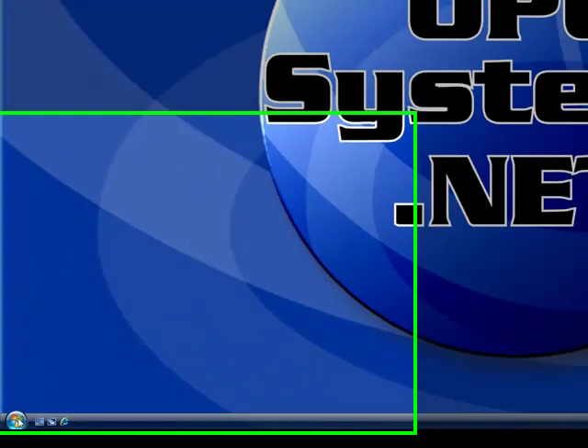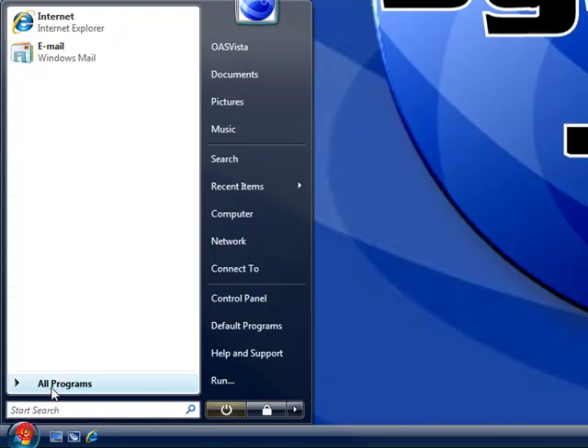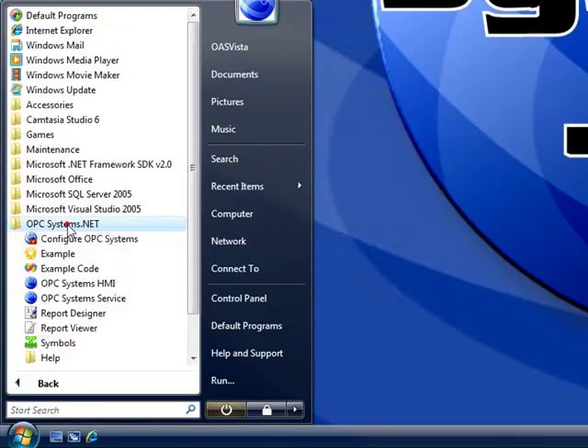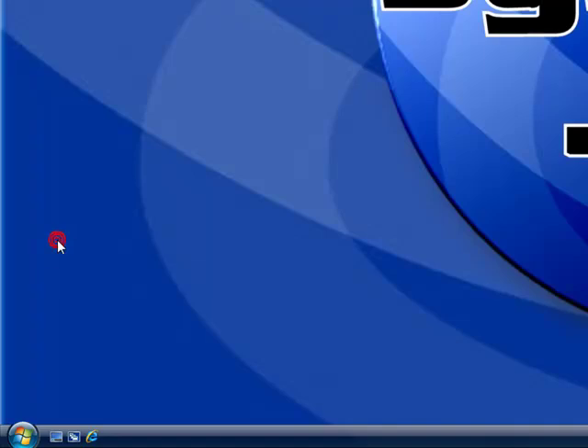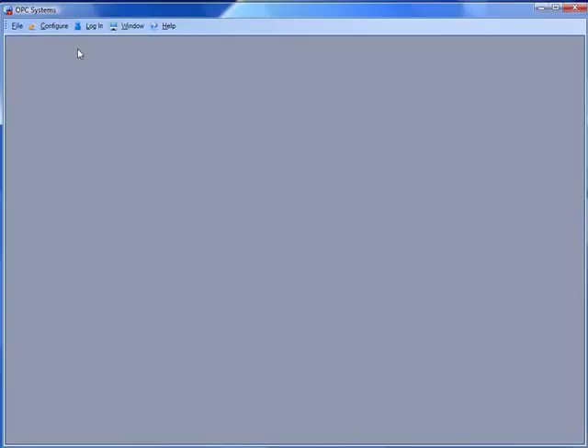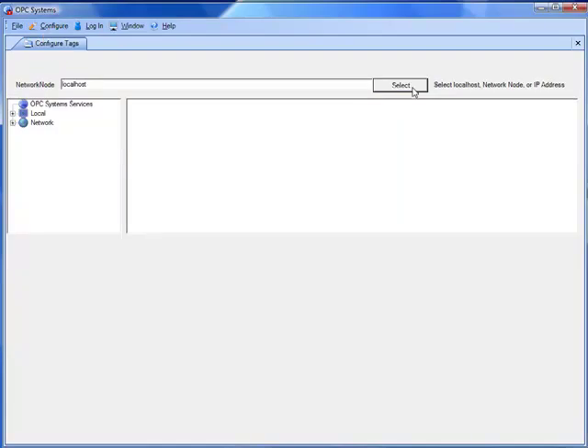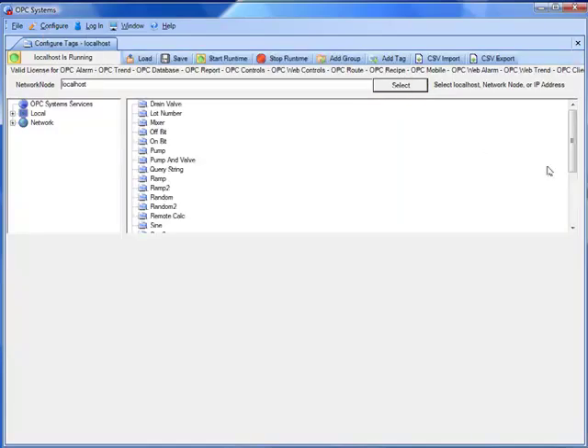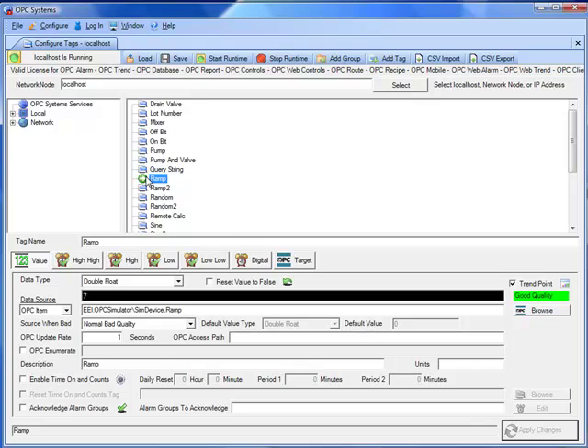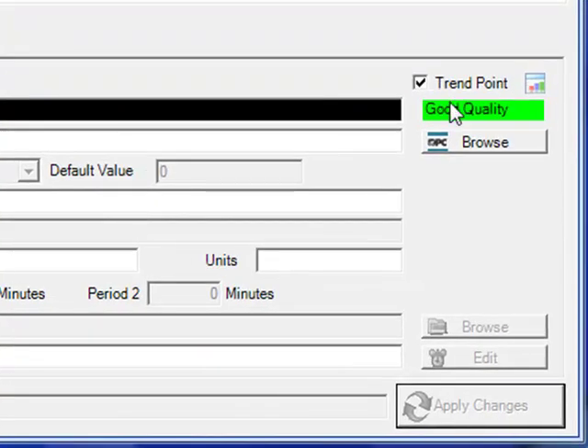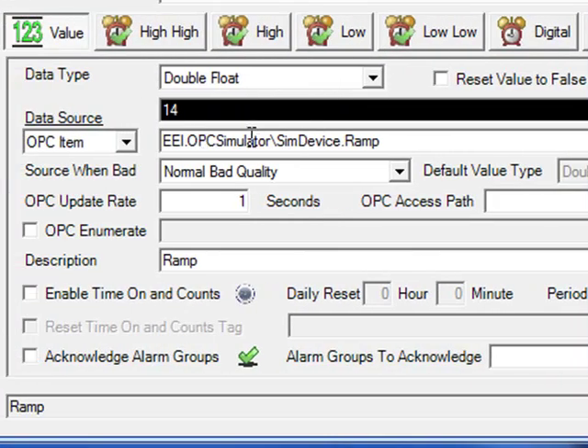Now let's see where that real-time data is defined. From the program group opcsystems.net, let's start the configure opcsystems application. If we look at configure tags and select the local service, we then see a list of tags from the demo configuration. Select the tag ramp. We see that an important property is enabled called trend point, and this tag called ramp is receiving data from an OPC item.